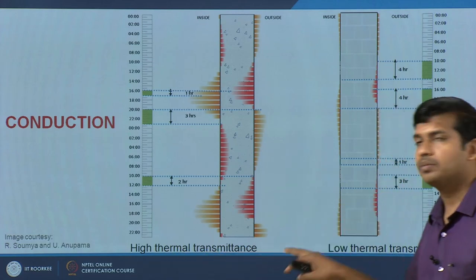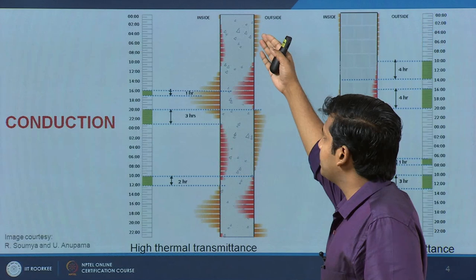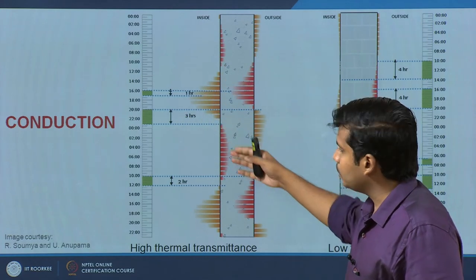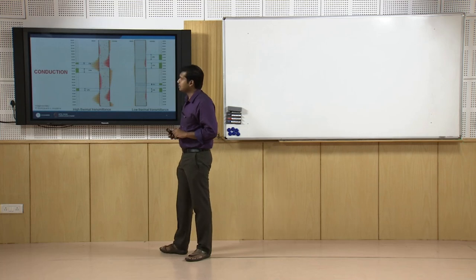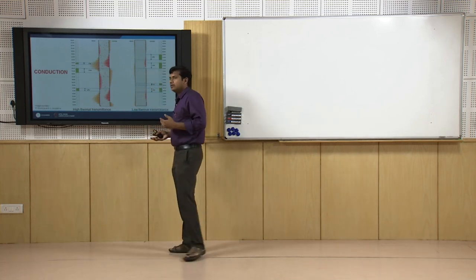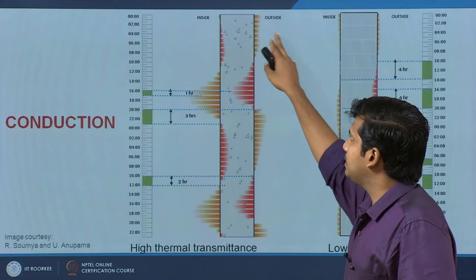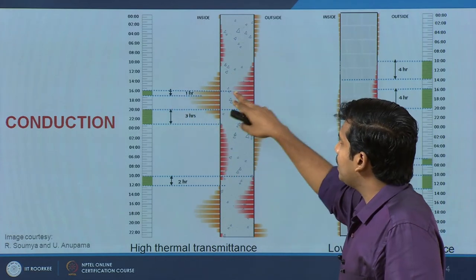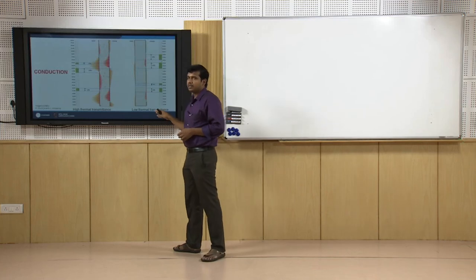This is a wall cross section: this wall has a high thermal transmittance, a highly conducting wall; and this is a low thermal transmittance, more closely an insulated wall. We looked at the rate of heat gain during daytime — this is a 48-hour, two-day cycle — where heat gain happens and then how it is transmitted indoors and reabsorbed and retransmitted outside. Two important things to note: the magnitude, indicated by bars, and the time it takes for the wall to conduct heat inside — between the ambient peak and the indoor peak, and to what extent heat gain happens indoors.